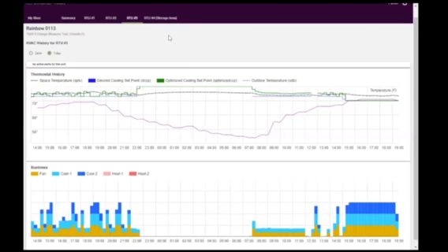Once it has that information, that's all it needs in order to start optimizing. The only inputs it needs beyond that are what the space temperature was in the previous 5-minute period. And it can, at that point, output what the settings should be for the next five. It uses predictive control to predict the best behavior over the next 30 minutes, but then every 5 minutes it recalculates the optimal value to say how many steps of each RTU need to be on in order to meet the comfort goals and also minimize how many of them turn on or off.